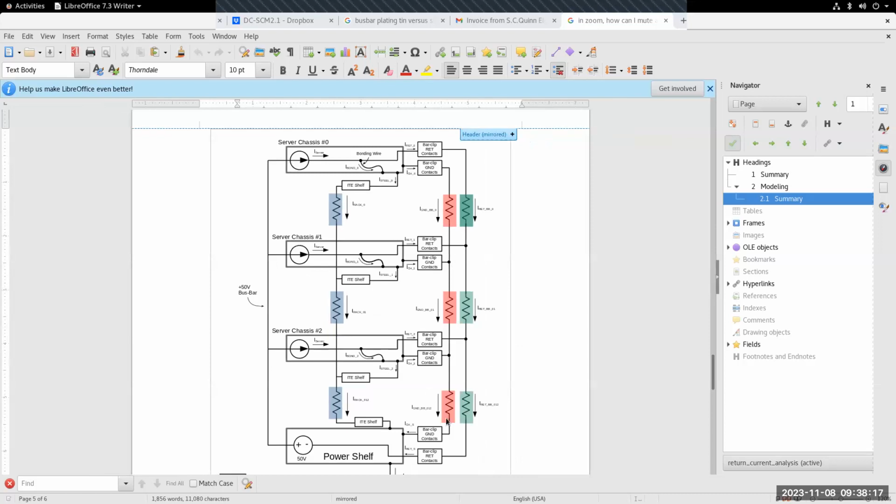For example, in one experiment we did, we put a power supply sitting in the bottom of the rack, connected to the bus bar, and I had two servers in the rack, one here and one up at the top. I'm sorry, what I have up here is actually an electronic load, so it's not a real server. It's taking power from the bar clip through the electronic load, but it's doing this with the return. The return is coupled to chassis, so the return current can go wherever it wants to go, on the bar clip or into the steel. It's very preliminary data, but it's interesting.